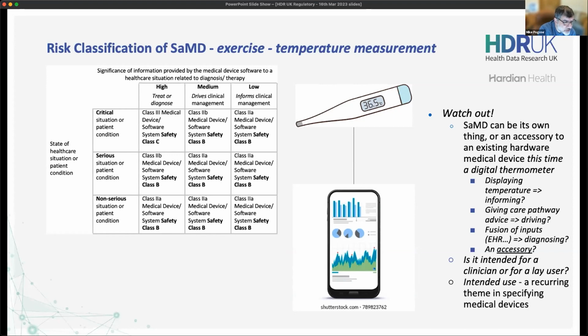Okay, so then you said sensors and the board were considered accessories. Well, yeah, and again, it depends. What is your product claim? That's an interesting point. Again, looking at the example on the screen of the phone software and the thermometer, which is the primary device and which is its accessory? You can look at it two ways. The thermometer, because it's got a display and you can use it in its own right for medical purpose, is the primary device. The phone is an accessory because it helps you see the data remotely, say. It helps use that device.